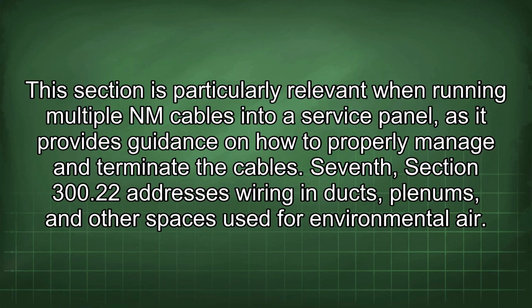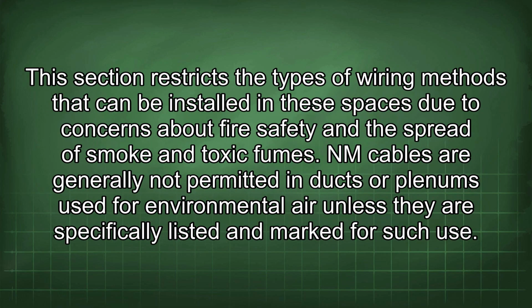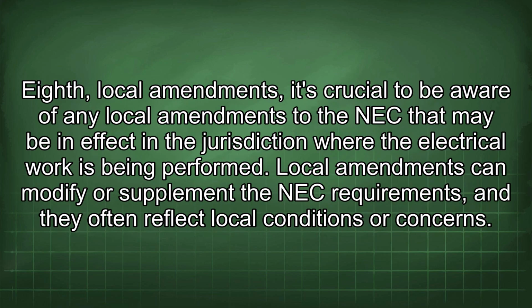Seventh, Section 300.22 addresses wiring in ducts, plenums, and other spaces used for environmental air. This section restricts the types of wiring methods that can be installed in these spaces due to concerns about fire safety and the spread of smoke and toxic fumes. NM cables are generally not permitted in ducts or plenums used for environmental air unless they are specifically listed and marked for such use. Eighth, local amendments.